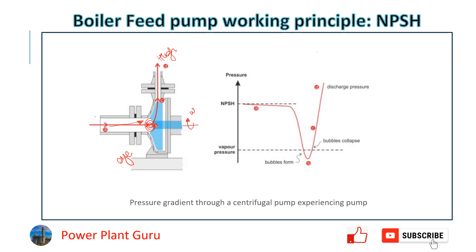Whatever static pressure is coming from the deaerator, because of the negative pressure phenomenon created at the eye of the impeller, the pressure reduces further at that point. As shown in the chart, whatever suction pressure is coming from the deaerator at the pump inlet, at the impeller eye the pressure reduces, and then again at discharge the pressure is high. Every centrifugal pump follows this phenomenon.